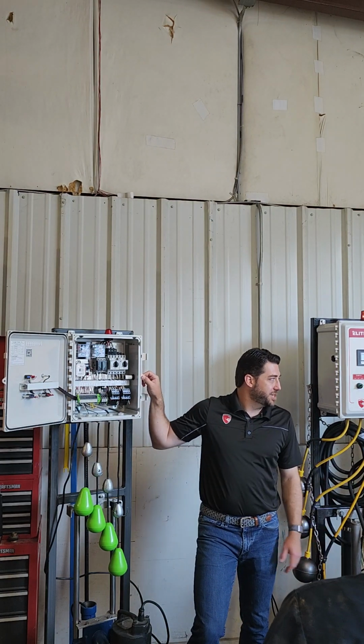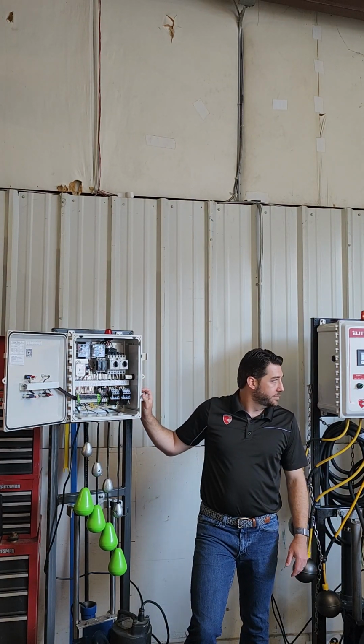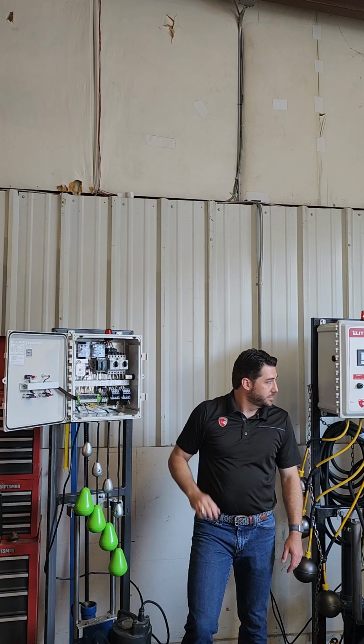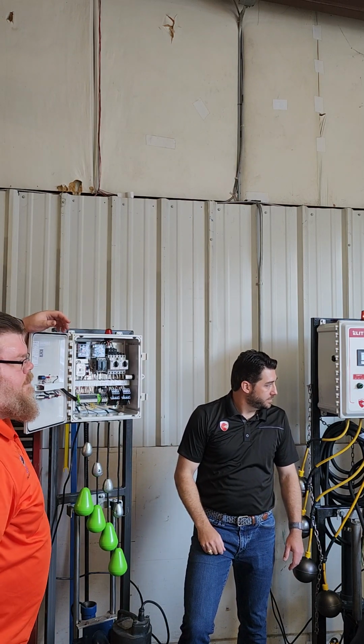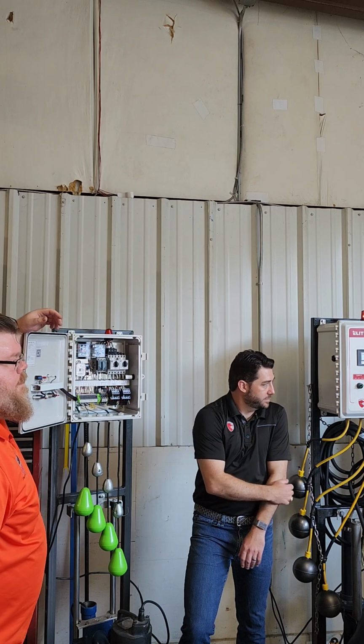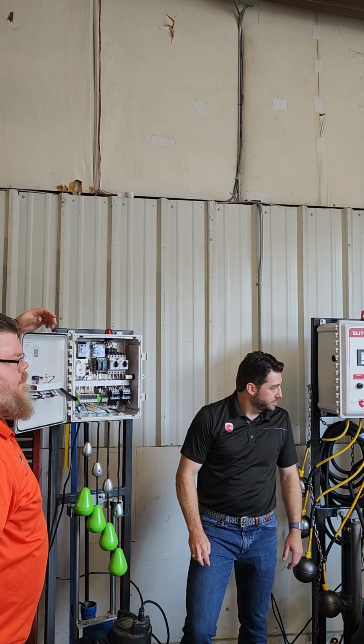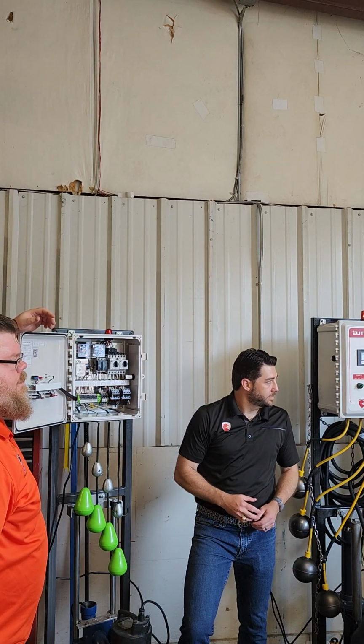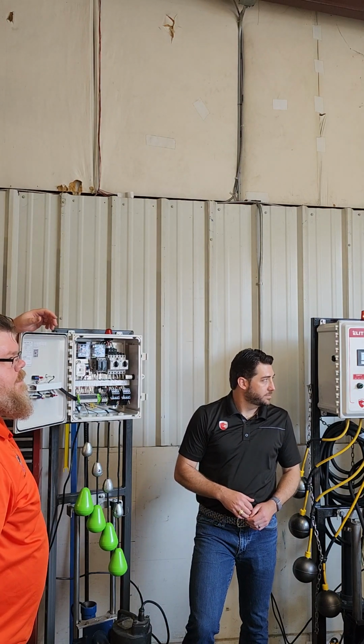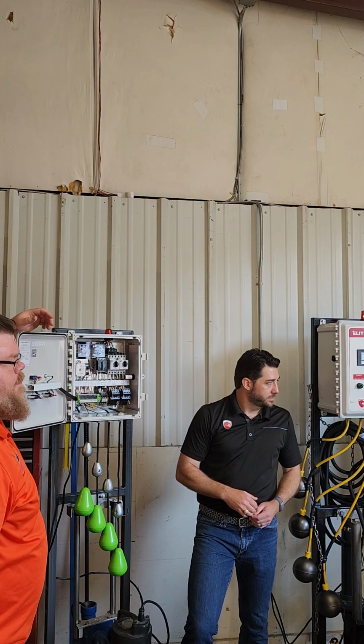Anything to add on to that, EJ? The overload is a heater. So if it's over amping, it's going to take maybe about 3 to 5 seconds for it to heat up, and then it'll trip. But if it's grounded, there is no wait. As soon as you turn it on, it'll snap. Put it in automatic. So that's indicating water, that's an issue with the motor.